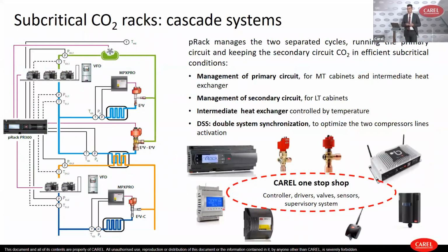Speaking about the cascade systems, what CAREL can provide is a one-stop shop solution, because we can provide not just the electronic controller, but also some different components that can be integrated into the units, like the valves, drivers, probes, but also the rest of the system, like the MPX Pro to control the cabinets, or Ultracella to control the cold rooms, and of course, leakage detectors and supervisory system to manage and have an overview of all the system.